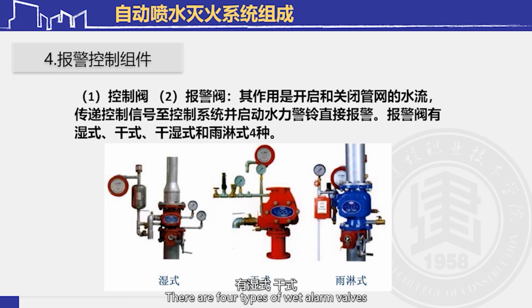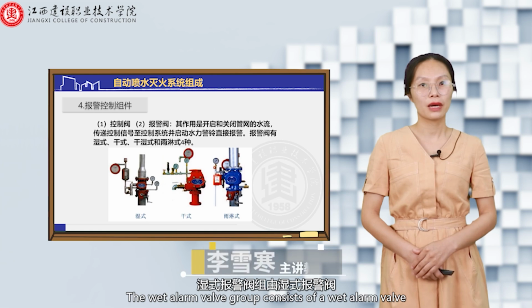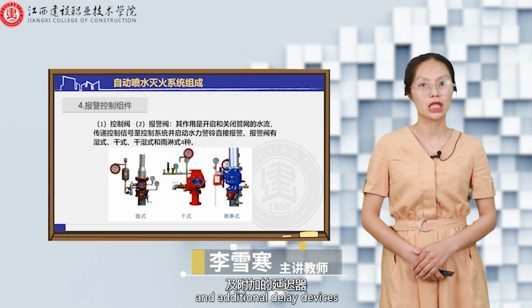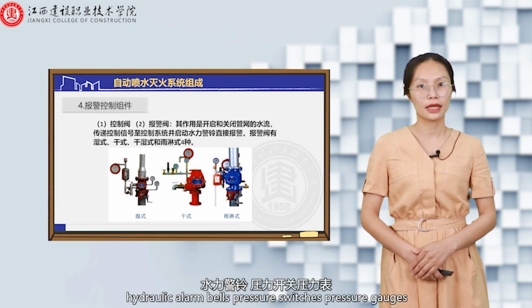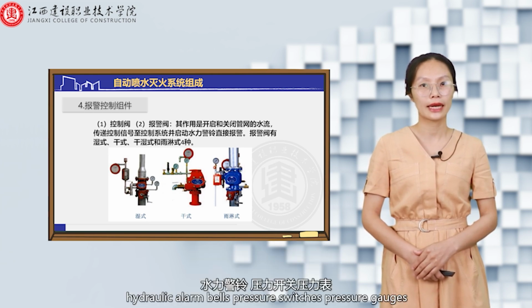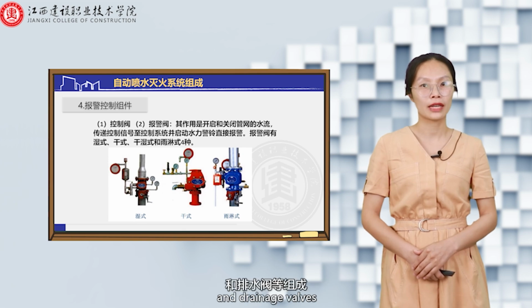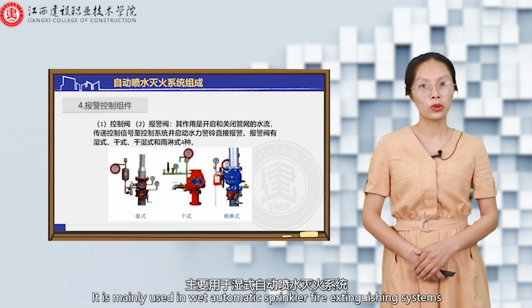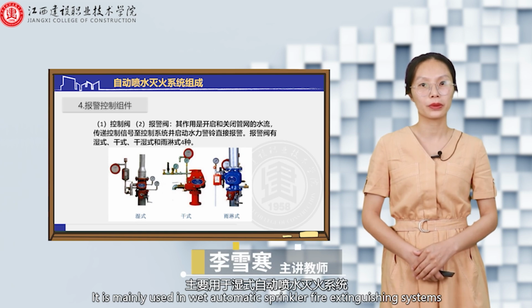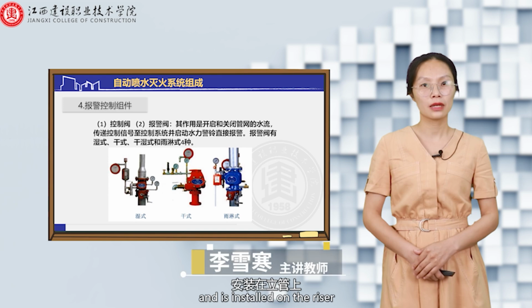There are 4 types of alarm valves: wet, dry, dry-wet, and deluge. The wet alarm valve group consists of a wet alarm valve and additional delay devices, hydraulic alarm bells, pressure switches, pressure gauges, and drainage valves. It is mainly used in wet automatic sprinkler fire extinguishing systems and is installed on the riser.